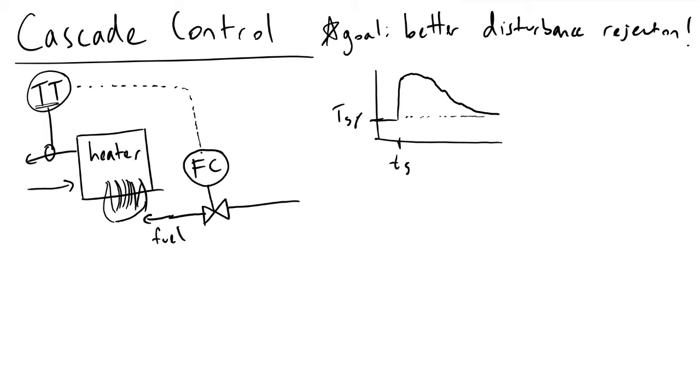What we get with cascade control is if we make use of an additional piece of information, such as the flow rate of the fuel, and we feed this information to our controller as well, we can implement nested feedback loops and realize much better disturbance rejection. We would return back to our desired set point value for our temperature much more quickly.